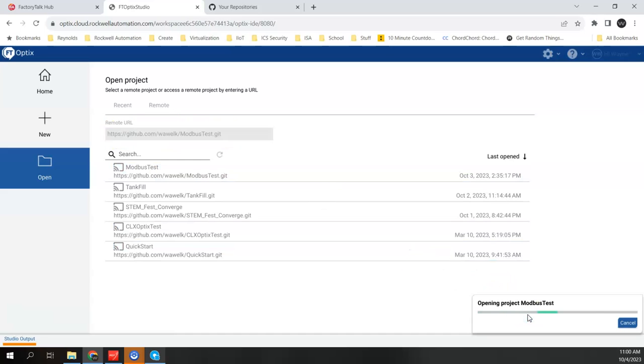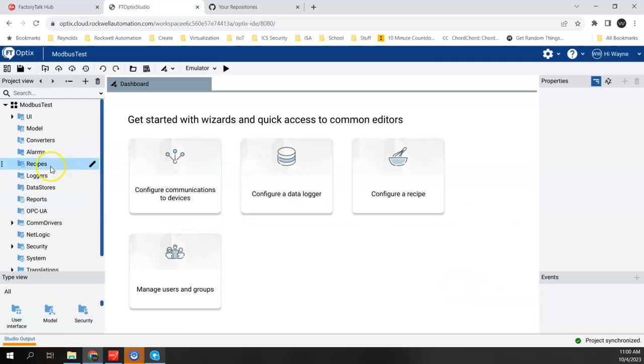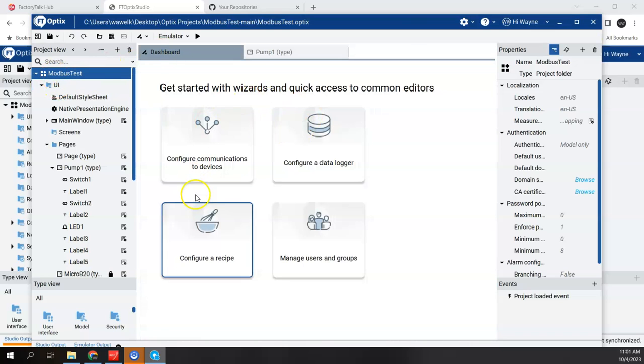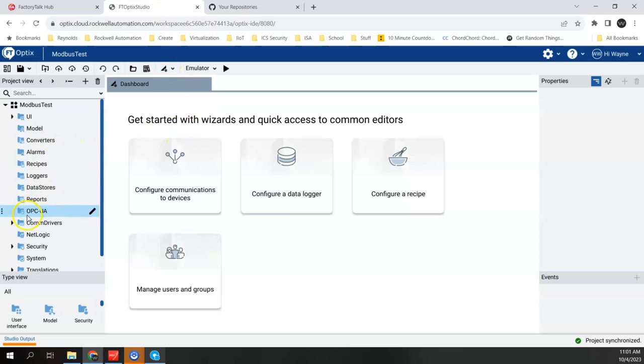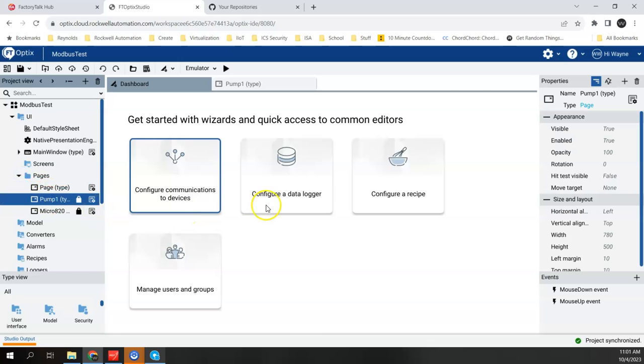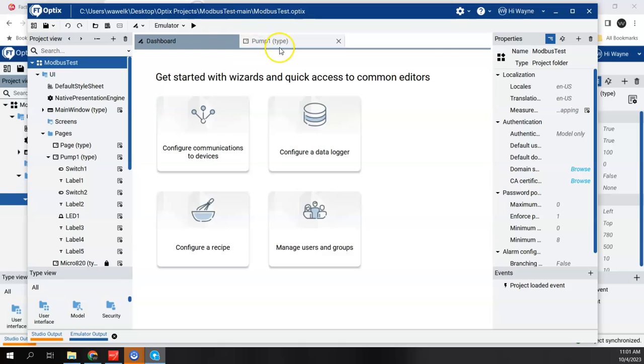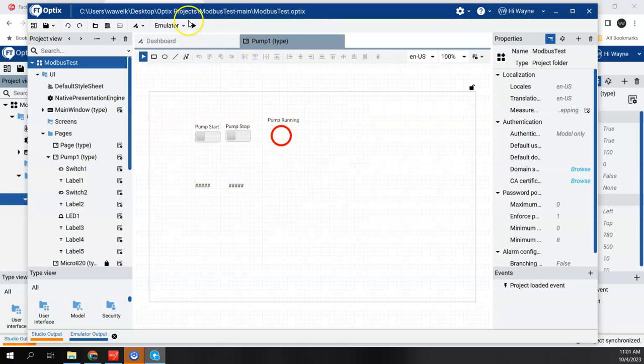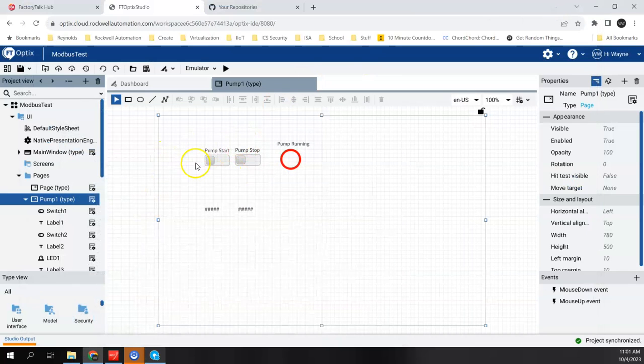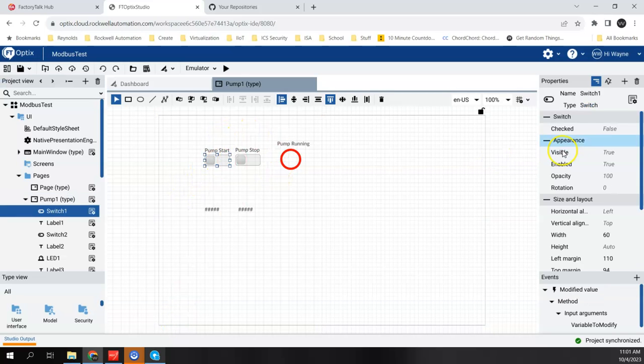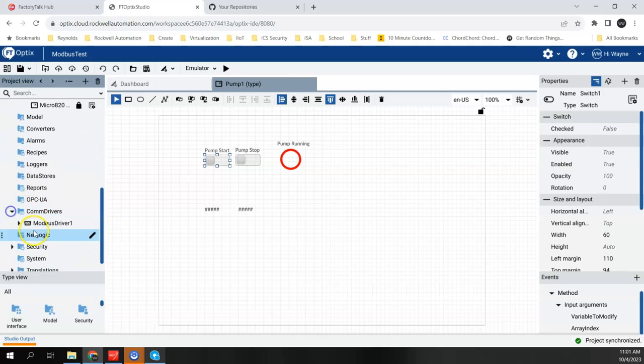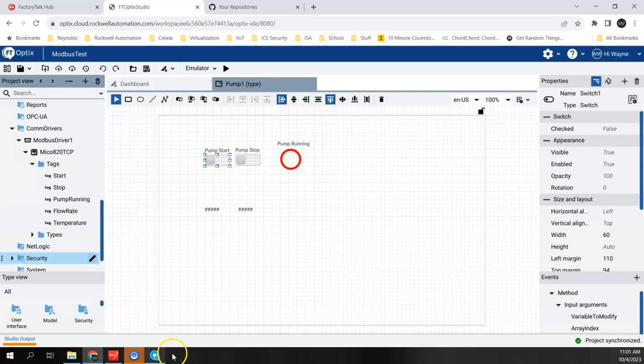When I do that, Studio in the cloud looks just like what I was seeing in my desktop Studio. If I go to Dashboard, I see the exact same thing. If I go to UI and then Pages — Pump One — here's my Pump One screen in the cloud. Coming back to my local installation, here's my Pump One screen — the same. I have the same editing capabilities in the cloud version as in the desktop version. I can click on elements, look at properties, assign tags, and over in COM drivers I have Modbus and the Micro 820 with all the same tags as in the local version.